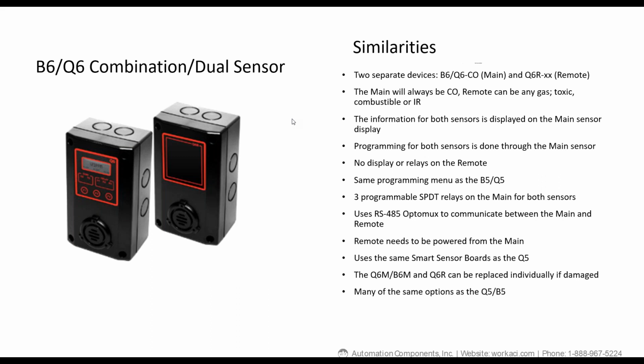So the nice thing about having this in 2 separate enclosures is that you can use that remote, that secondary gas can be anything. It could be to measure gasoline vapors or petroleum vapors. They're normally heavier, so you're going to mount that down low. Or that secondary sensor could be methane or hydrogen, and that would be mounted high up near the ceiling.